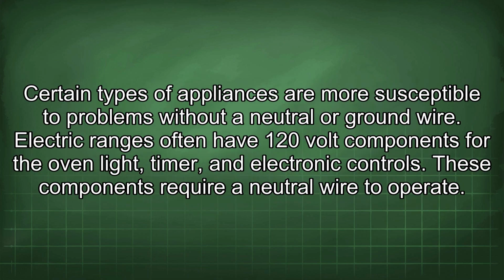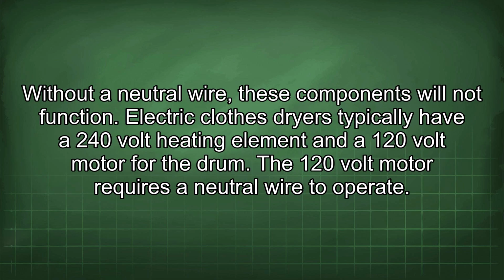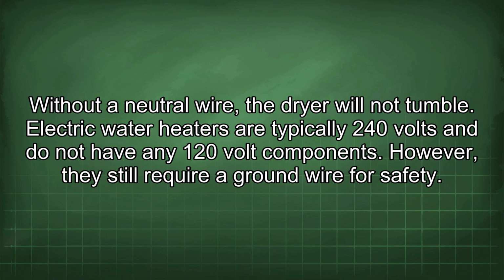Certain types of appliances are more susceptible to problems without a neutral or ground wire. Electric ranges often have 120-volt components for the oven light, timer, and electronic controls. These components require a neutral wire to operate. Without a neutral wire, these components will not function. Electric clothes dryers typically have a 240-volt heating element and a 120-volt motor for the drum. The 120-volt motor requires a neutral wire to operate. Without a neutral wire, the dryer will not tumble.